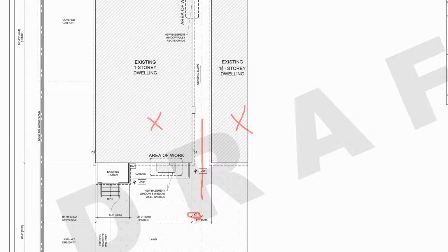With the building code, there's a limiting distance of 1.2 meters between you and the next building face, or the property line, I should say, not the building face. So that distance needs to be 1.2 meters for you to be able to put in windows, and that's to limit the spread of fire from one building to the next. So we're roughly half that. We're like 0.63 meters, something like that. So unfortunately, it's not even that close for a traditional window, that is.